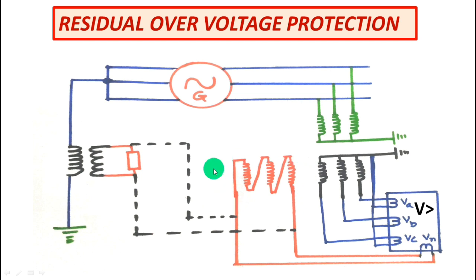That this PT winding rating should be 110 by 3, not the 110 by root 3. Suppose if this is an 11 KV generator. So you will using this PT, this phase voltage will be 11 by root 3 by 110 by root 3. But here this winding winding rating will be 110 by 3.